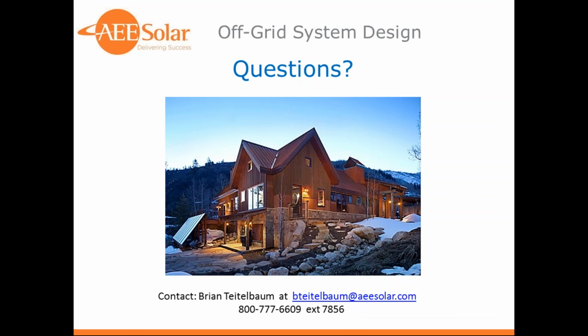That's a good question. I think they're all fairly much in the same place. I mean, even lithium is in the maybe mid to lower 90% efficiencies. The aqua and saltwater batteries are pretty much in that realm. Doesn't seem to be a whole lot of difference in the efficiency of the batteries at this point. Essentially, you take a certain amount of energy out of a battery, you have to put more energy in to get it full again. And that energy is typically lost as heat inside the battery.